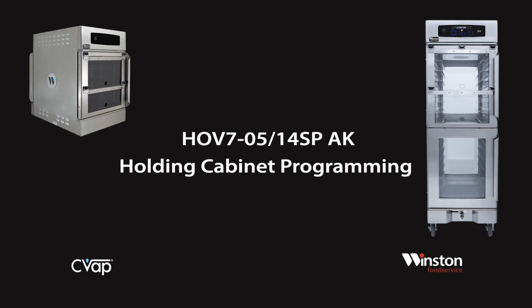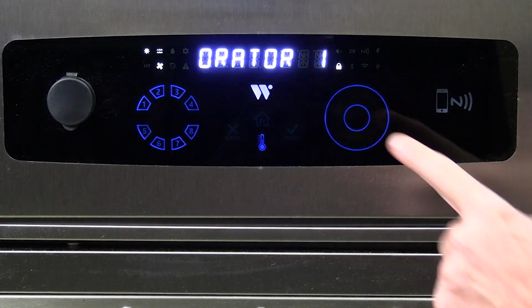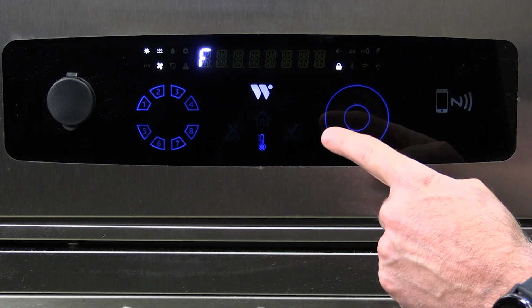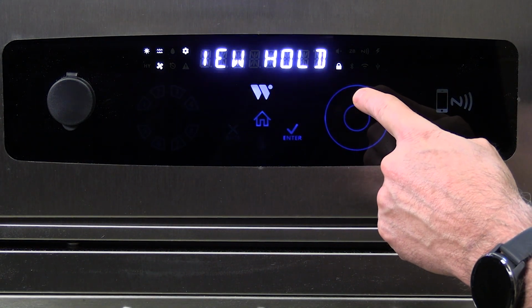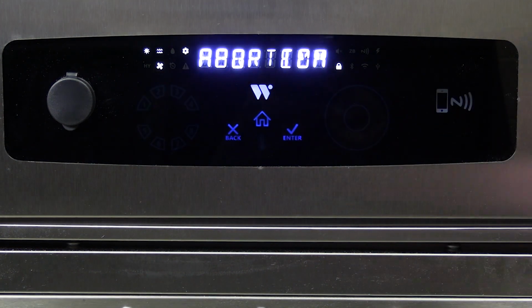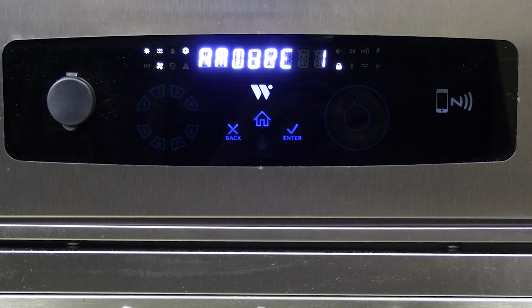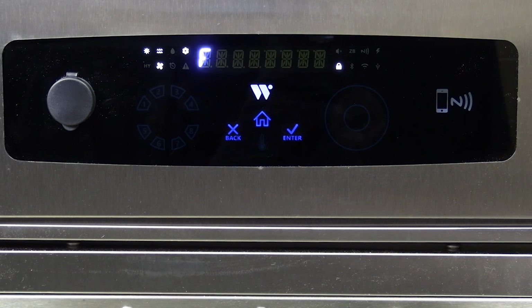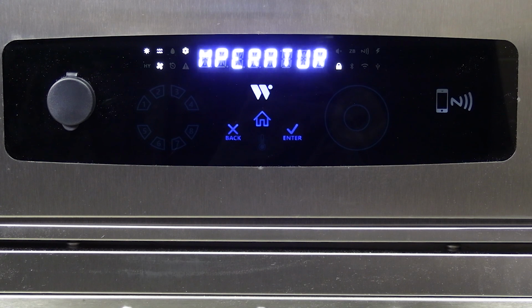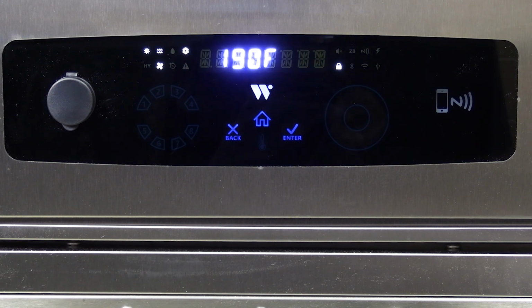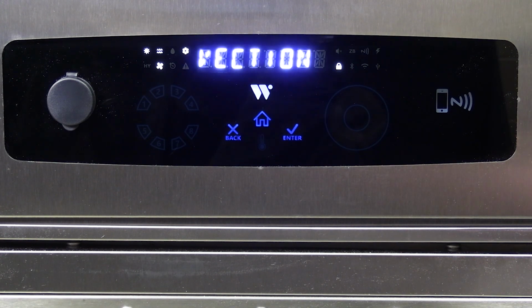Controller navigation and programming. Trace the navigation wheel in a clockwise motion. View hold settings will be displayed. Select Enter. The controller will now display the vapor temperature setting, the air temperature setting, and the convection fan setting.